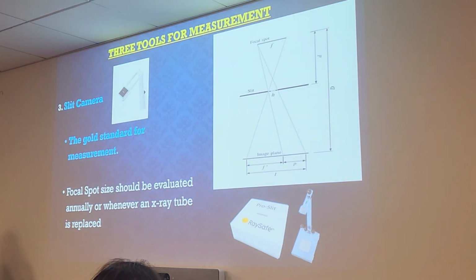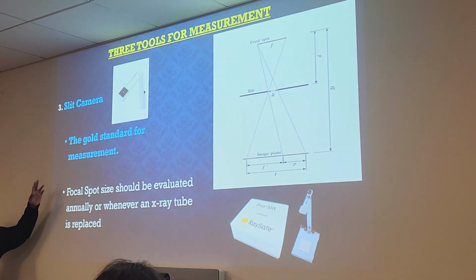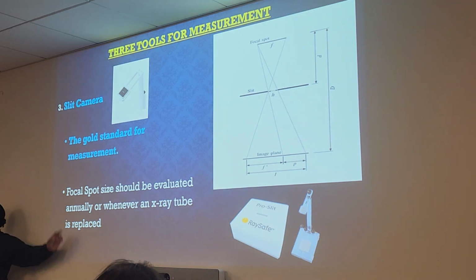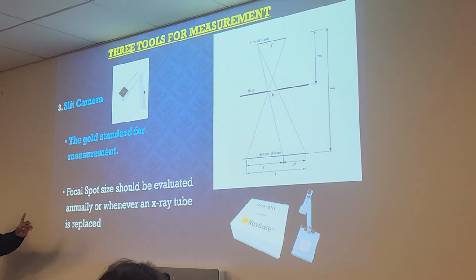And the next one is the slit camera. So this is the one that medical physicists now mainly use because it's easier to use. All you do is just take this little aperture, put it in between the tube and your IR. All you have to do is make 2 exposures, one at a perpendicular angle, one at a parallel angle, and it gives them the measurement for their focal spot. So this one is much easier than the pinhole. So it's just 2 exposures at like 90 degrees to each other.